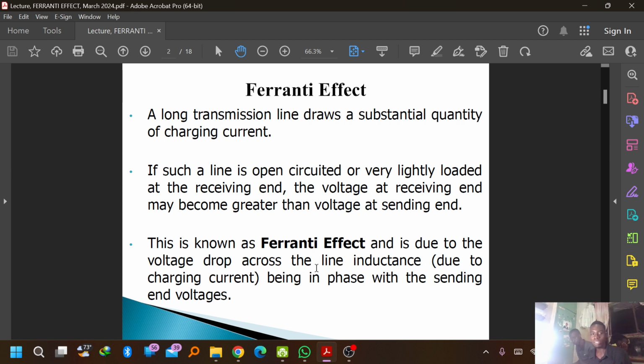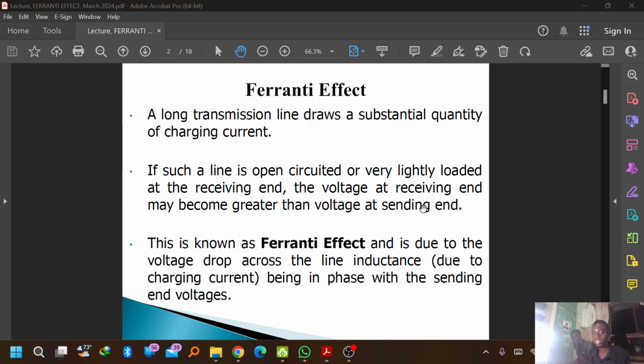So the main point to note is around this point. They're saying if a long transmission line is lightly loaded at the receiving end, or is open circuited, meaning not loaded, the voltage at the receiving end may become greater than the voltage at the sending end. And that phenomenon is called the Ferranti effect. So what is Ferranti effect?